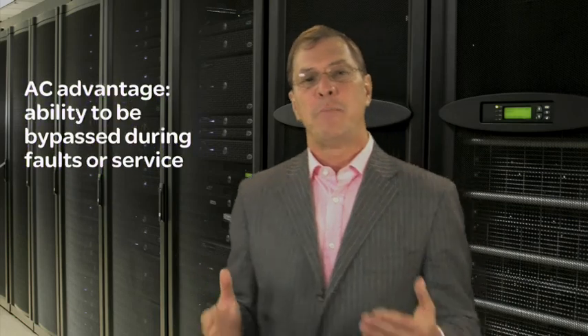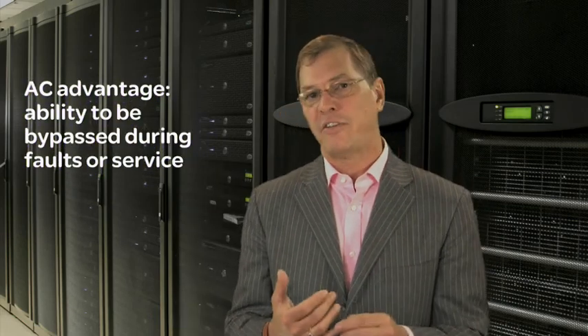The AC system, on the other hand, has a slight advantage because it has the ability to be bypassed during faults or service. As we are well aware, most AC UPS systems have both a static and a maintenance bypass. So when they either are maintained or if they experience some kind of fault, the load can be transferred around them back to the AC source. That function of a bypass improves the availability of the AC system considerably.